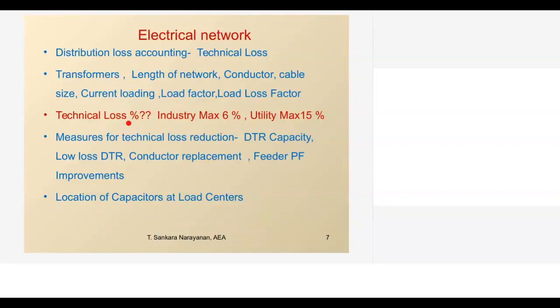So technical loss in industry, if you go by the IEEE standard, can go up to a maximum of 6%. Then as per the Central Electricity Authority guideline, for a utility, technical loss can go up to 15%. Commercial loss is a separate issue. Commercial loss is purely an administrative matter. Otherwise, technical loss, how far we can reduce it. Some of the utility companies add a DTR. So if there is a 200 kVA DTR, they will add one more parallel DTR so that loading is taken care of and the load loss is reduced.